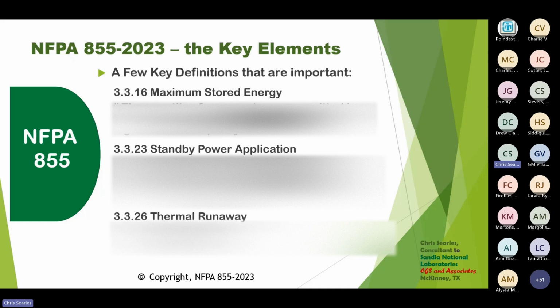That's one of the complexities of this whole circumstance. Thermal runaway has been defined within 855. There are different definitions out there, but self-heating of an electrochemical system in an uncontrollable fashion. With a lithium battery, you may have a thermal runaway condition without necessarily creating a fire, but you could have the release of toxic gases and could actually have an explosion without a fire. It may be a little bit unusual, but it can happen.